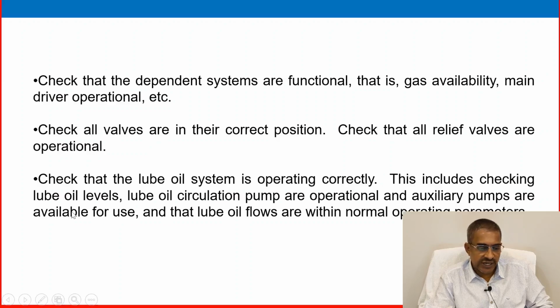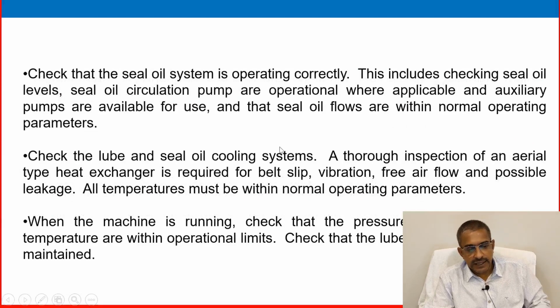This includes checking lube oil level, lube oil circulation pumps are operational, and auxiliary pumps are available for use, and that lube oil flows are within normal operating parameters. Check that the seal oil system is operating correctly. This includes checking seal oil levels, seal oil circulation pumps are operational, where applicable, and auxiliary pumps are available for use, that seal oil flows are within the normal operating parameters.